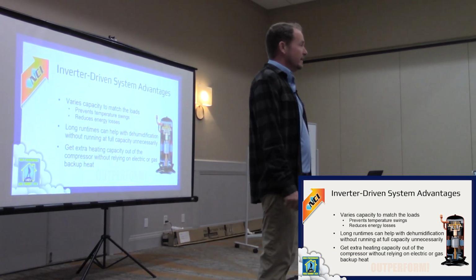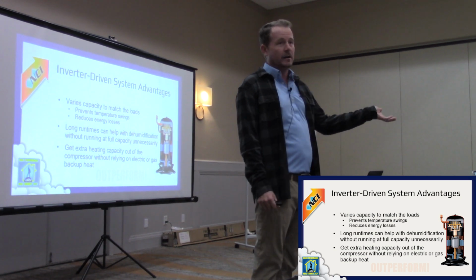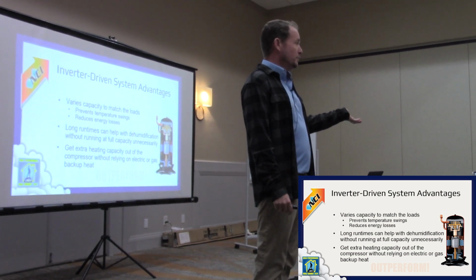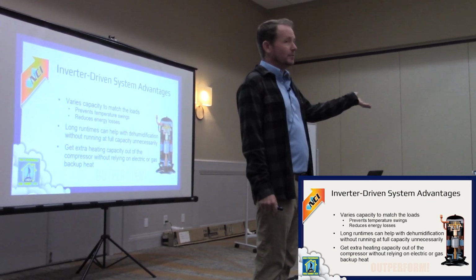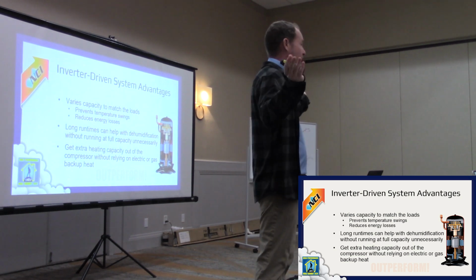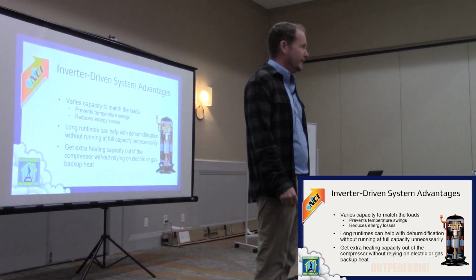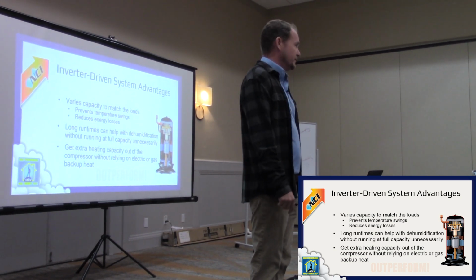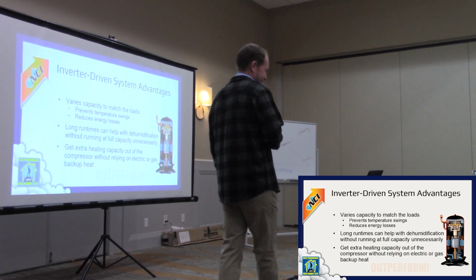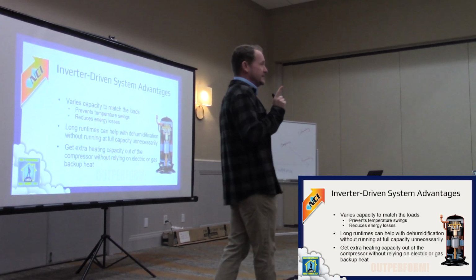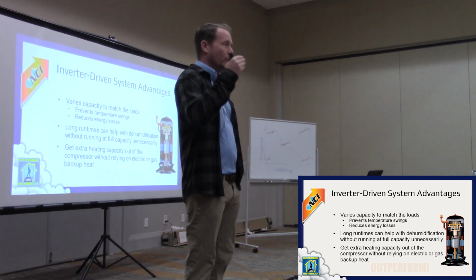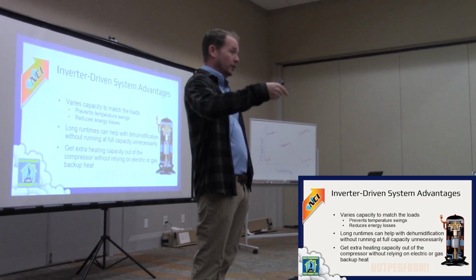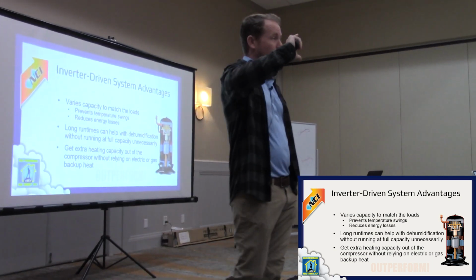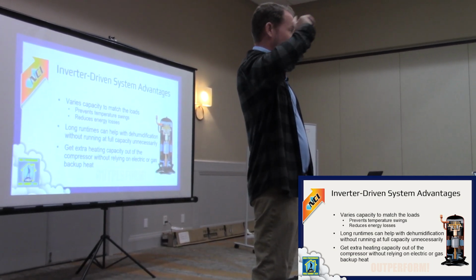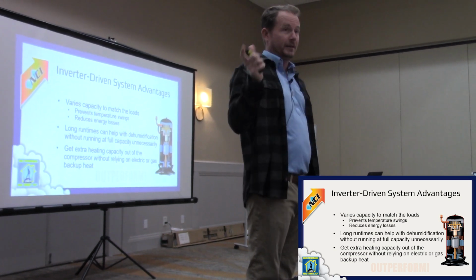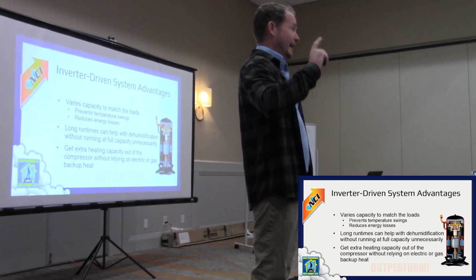It's funny, you pull out this old stinky 8-SEER with the dirty evaporator coil, and you put in a brand new inverter-driven variable speed system, and all of a sudden the humidity's higher in the house. We tell the client they're just crazy, but they're not, a lot of times. There's reasons for that, and it comes down to what you're trying to accomplish. If you're trying to overcome bad ductwork by spinning a blower faster and don't address that, you're going to have major problems.